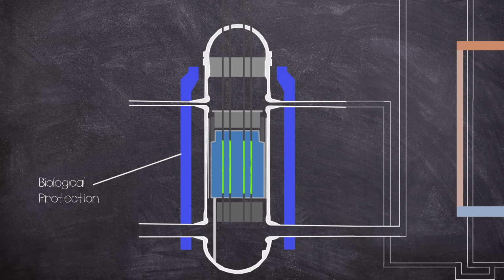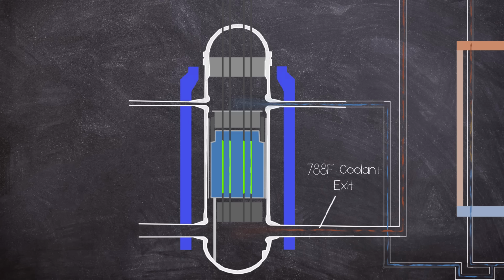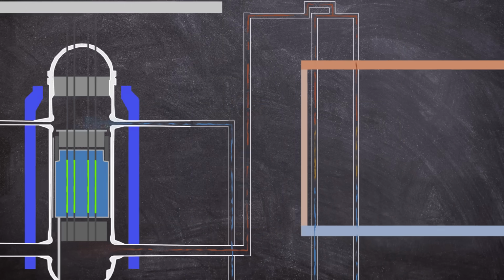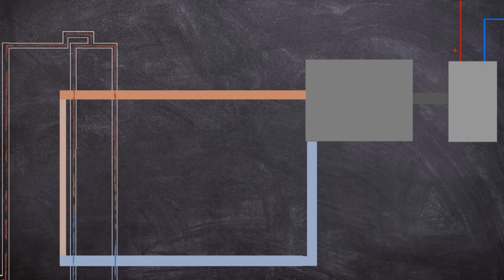Surrounding this whole arrangement was a water tank forming the biological protection. The reactor produced power by heating up the coolant CO2 gas. It exited the pressure vessel via pipework at a temperature of around 420 degrees centigrade, aided by a turbo compressor, which then made its way to 6 steam generators, which then pushed the turbines, which created the tasty electricity.